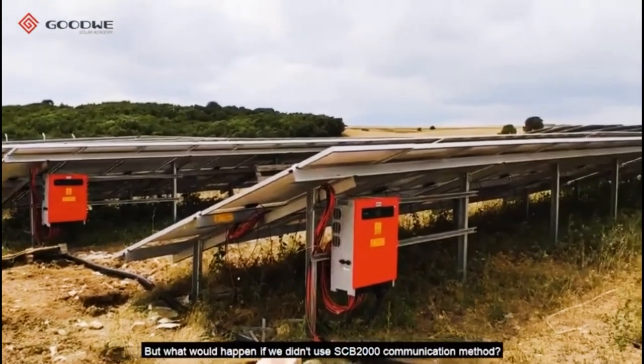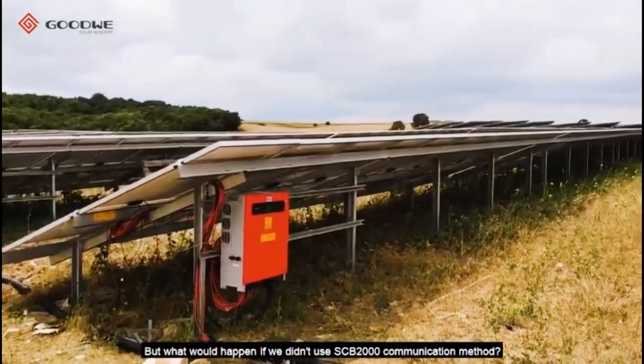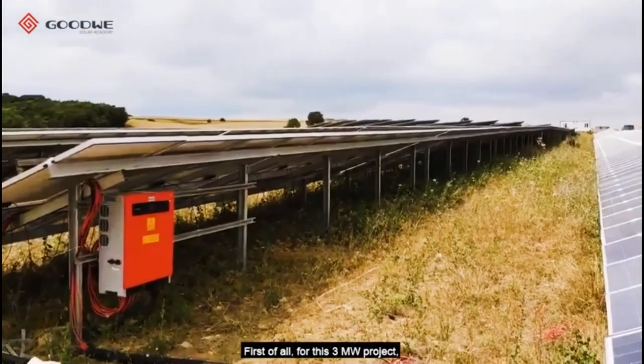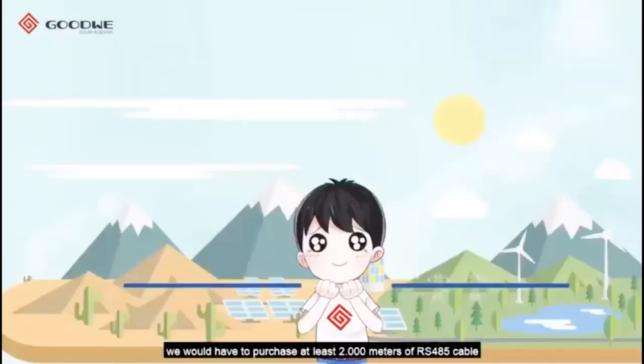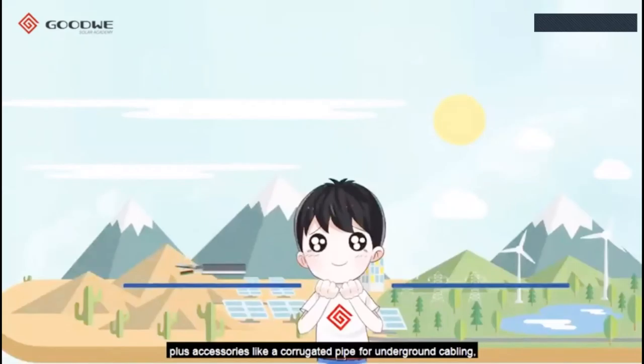But what would happen if we didn't use the SCB2000 communication method? First of all, for this 3 MW project, you would have to purchase at least 2,000 meters of RS-485 cable, plus accessories like a corrugated pipe for underground cabling, and also extra labor costs would be added. Installation costs would be higher at bigger projects.